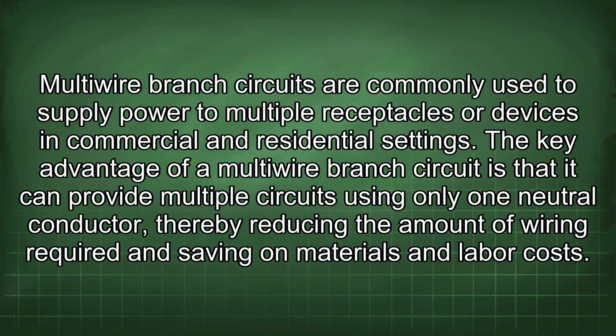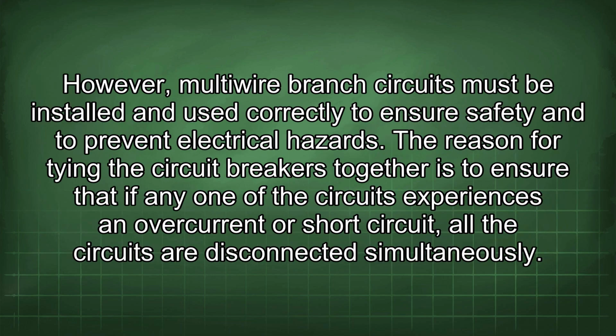Multi-wire branch circuits are commonly used to supply power to multiple receptacles or devices in commercial and residential settings. The key advantage of a multi-wire branch circuit is that it can provide multiple circuits using only one neutral conductor, thereby reducing the amount of wiring required and saving on materials and labor costs. However, multi-wire branch circuits must be installed and used correctly to ensure safety and to prevent electrical hazards.